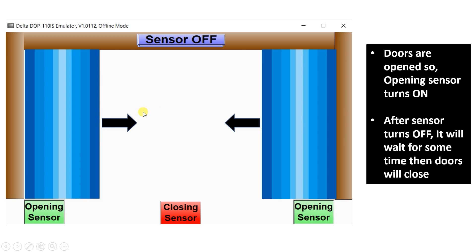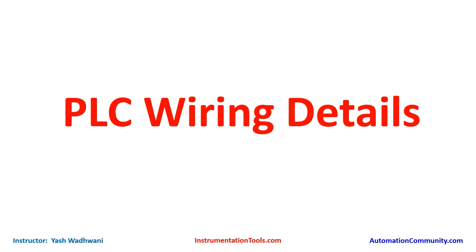When the person passes through, the sensor will turn off. The system will then wait for five seconds. If within those five seconds a person comes across again, it will stay in the current state. Otherwise, if there is no human presence and the sensor is off for five seconds, the doors will try to close. The closing sequence is door one forward and door two reverse, moving until the closing sensor is sensed, then the system will stop.